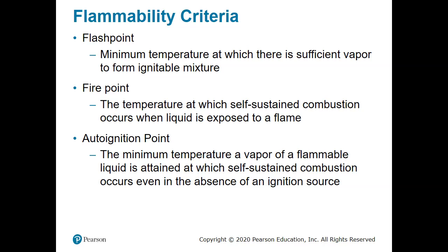So the difference between flashpoint and firepoint is sustainability. Again, the flashpoint is just that. It is a flash. It's a flash in the pan. It ignites, it goes out, all within microseconds of each other. Firepoint, it lights, it stays lit. But I need to introduce a match or a flame or something to it to get it to light. Striker, flint, something, spark.